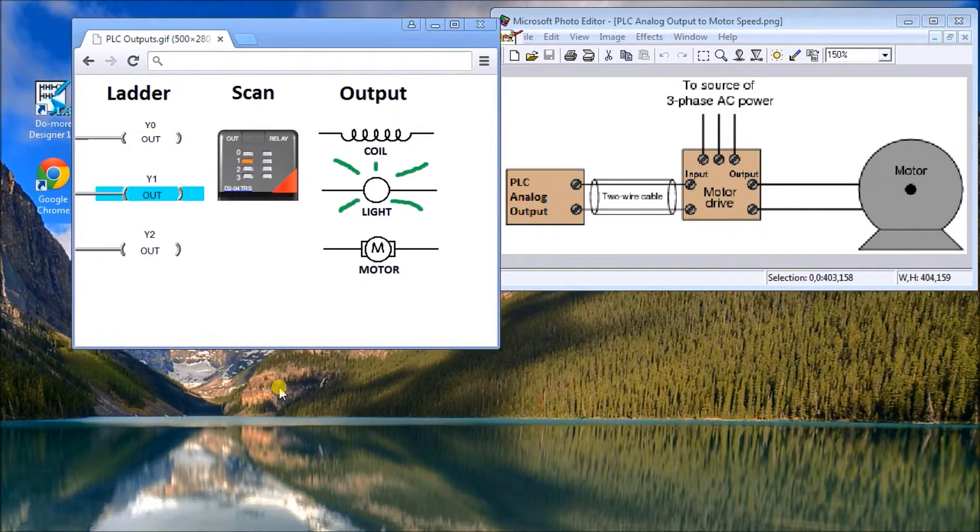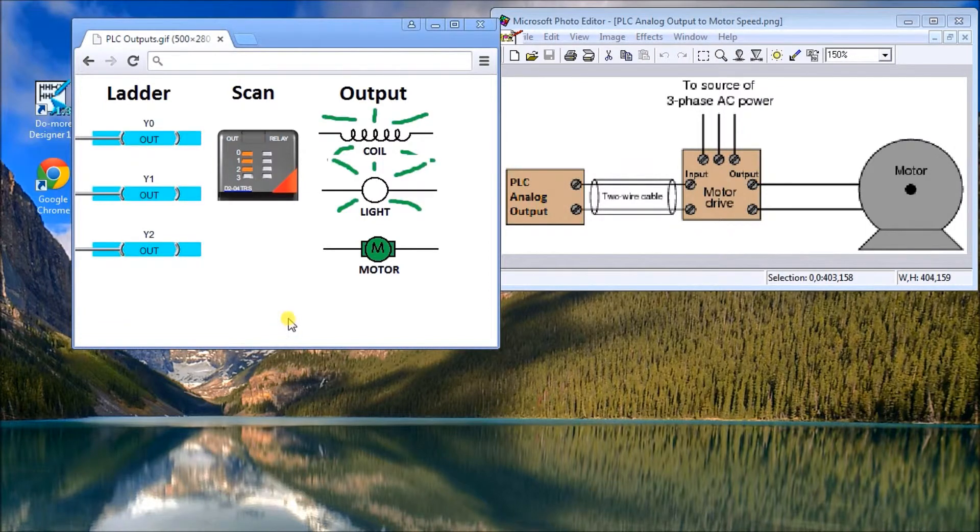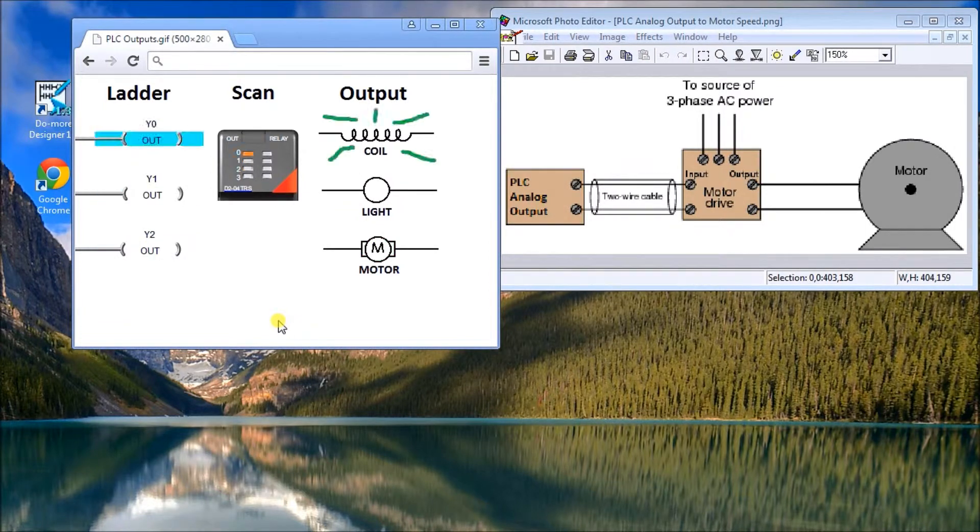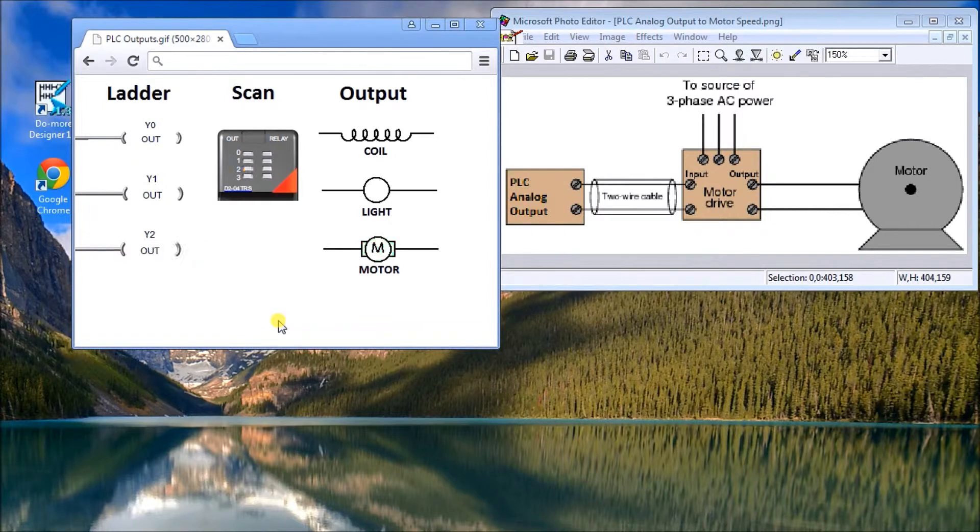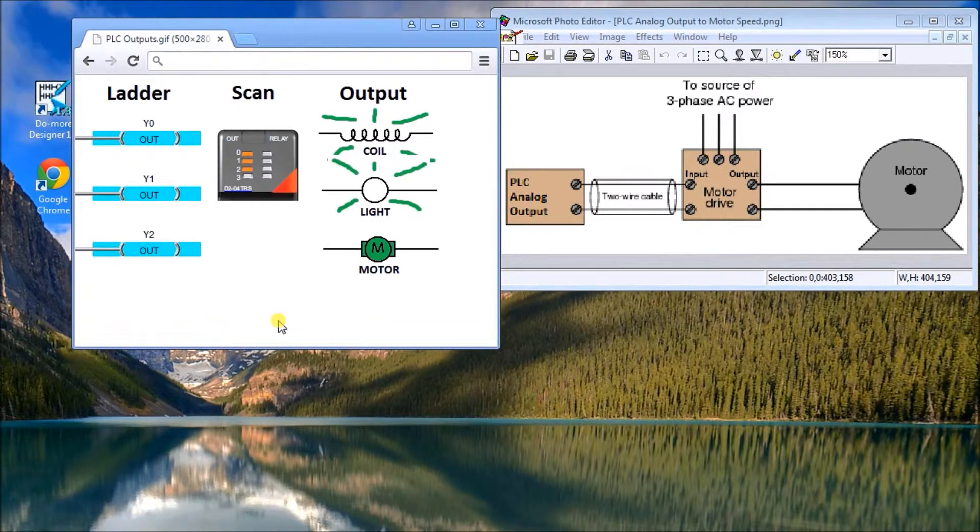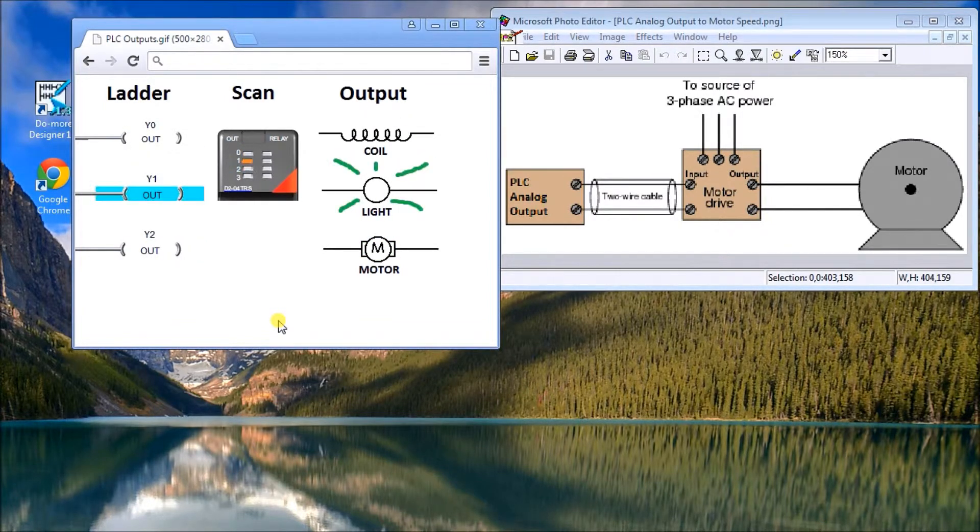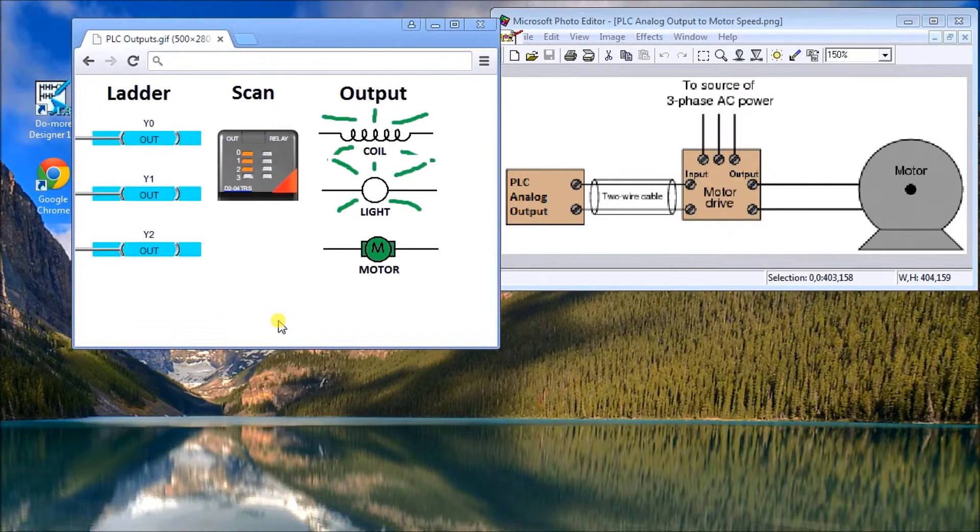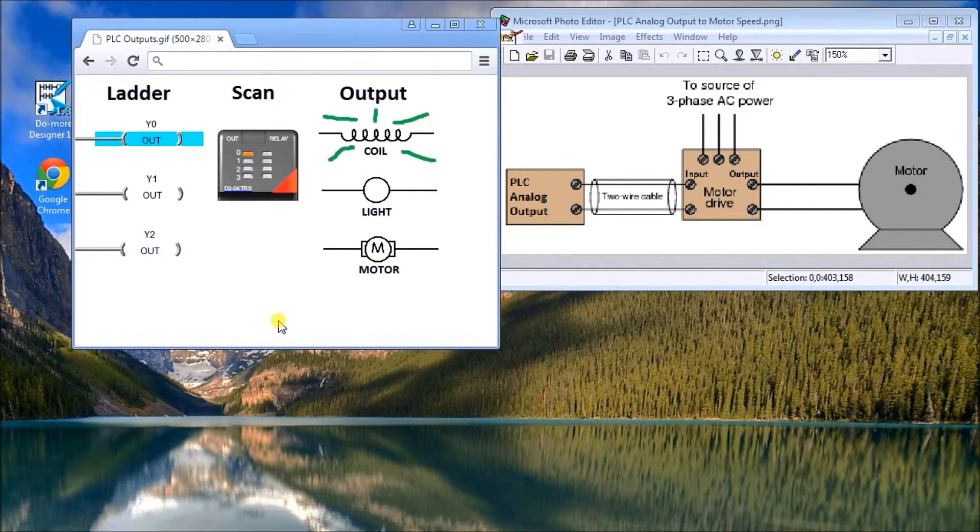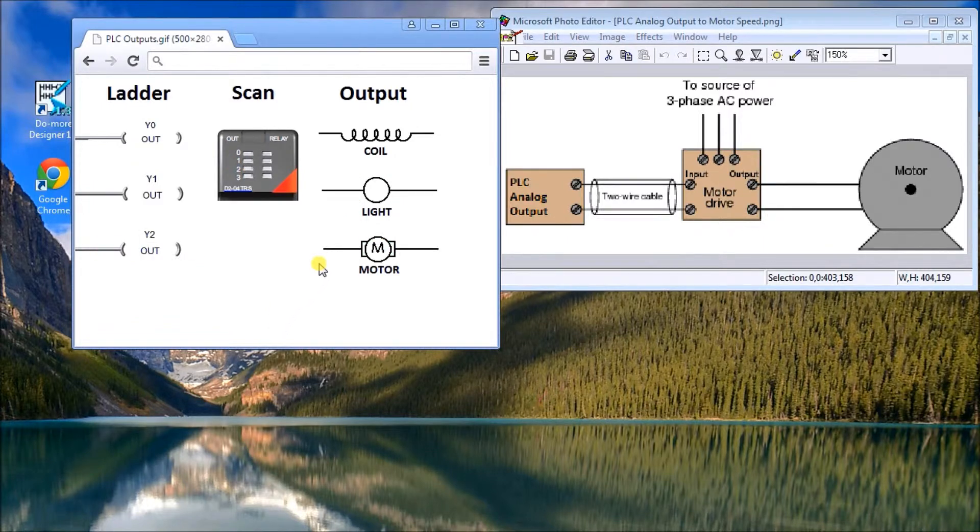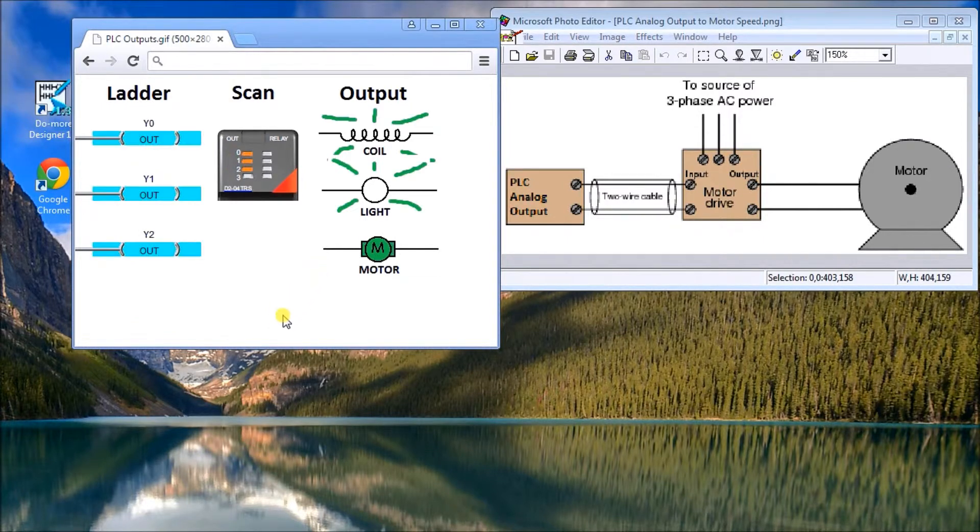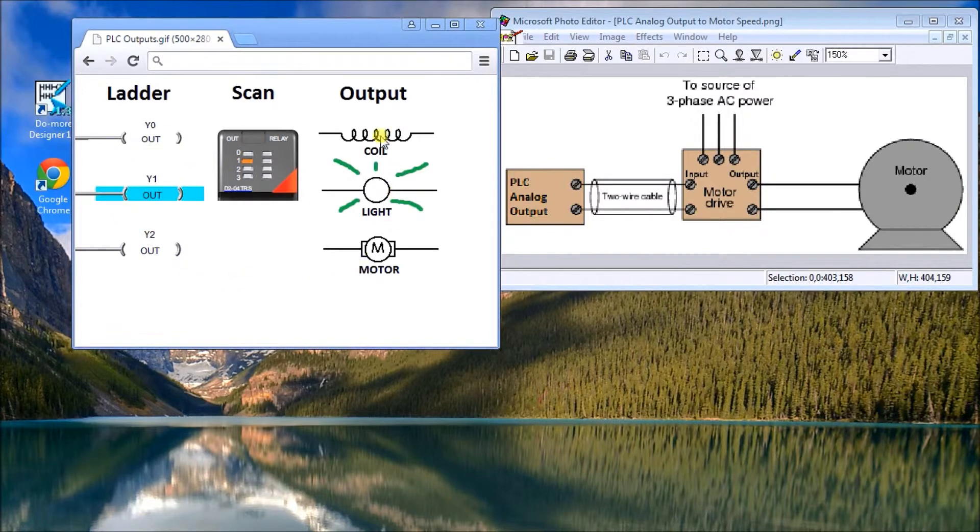The first one being discrete, meaning on and off, and the second one being analog that gives you a voltage or current range. Typically 4 to 20 milliamps for current, and for voltage 0 to 10 or 1 to 5, something in that sequence. If we look back at this diagram here, these are all my discrete outputs.